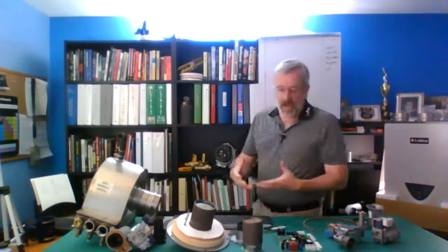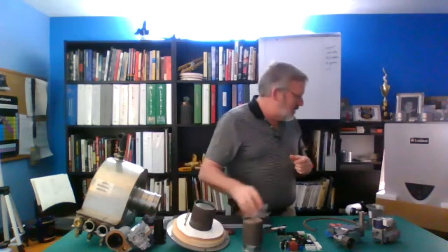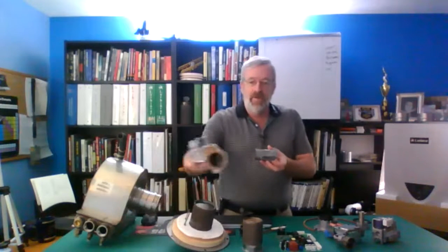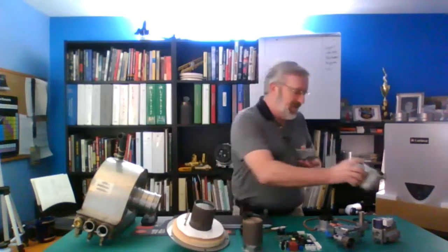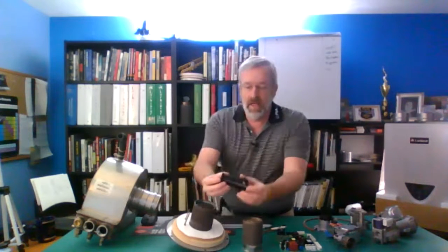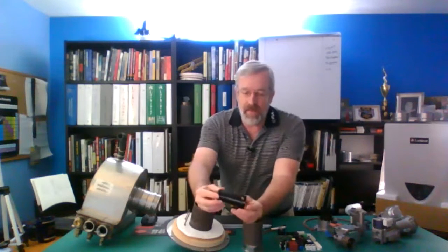So how does that all work? How does that venturi work? Well, right now, residentially out there in the field, there are two styles of the venturi. There is the older 5-to-1 style venturi, and that's this assembly, which mounts on the side of the Honeywell gas valve. Now, I was able to get it apart this morning, which makes it a little easier to see. This is the insert that is inside of this venturi here, and that helps to really explain how it works. And the venturi itself is a couple of pieces.